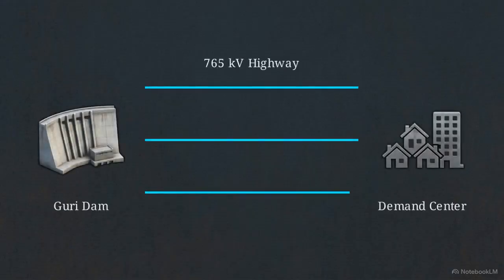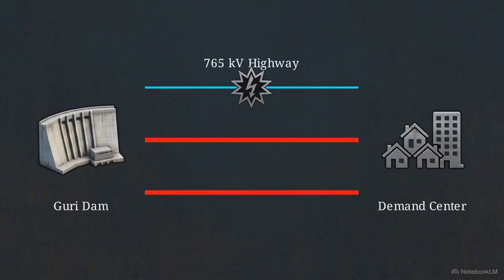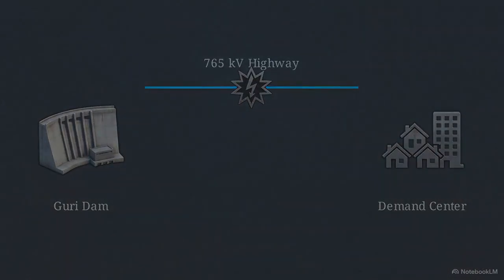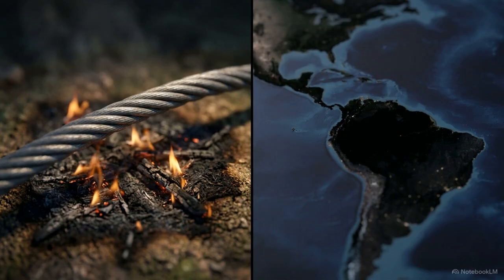This disconnection created an electrical vacuum. Energy from the dam was forced instantaneously onto the remaining parallel lines. Pushed past their thermal limits, these lines tripped offline. The entire electricity highway was severed. The blackout began because a localized safety mechanism functioned exactly as designed. By saving a single line, it initiated the sequence for a nationwide collapse.